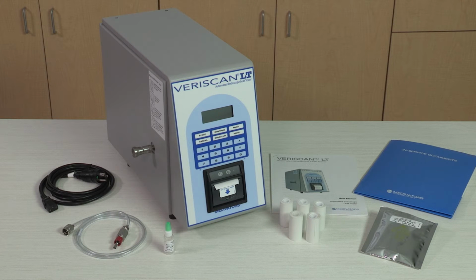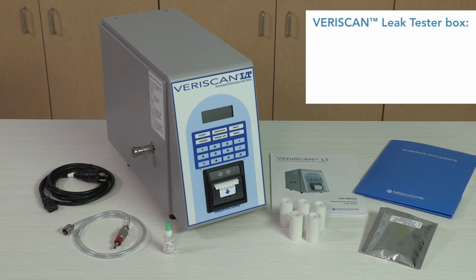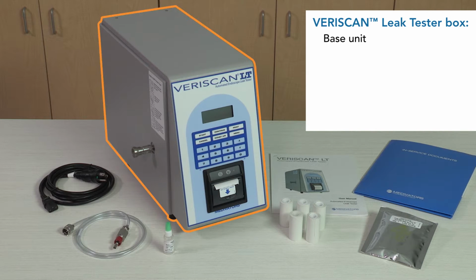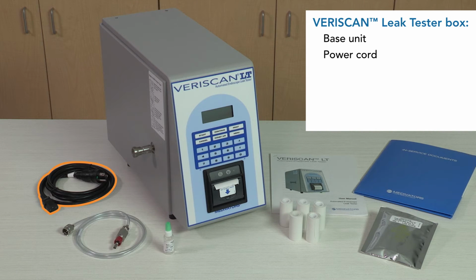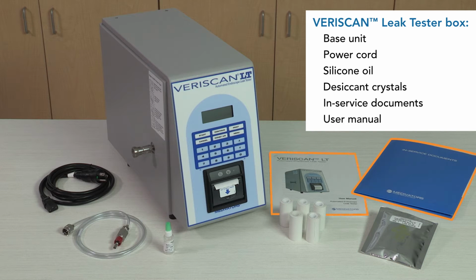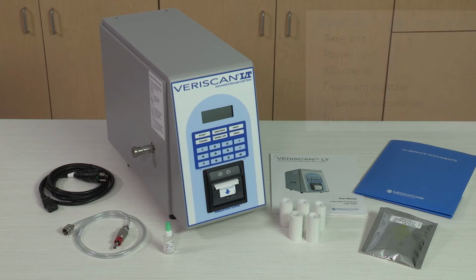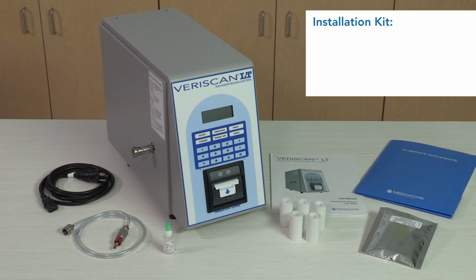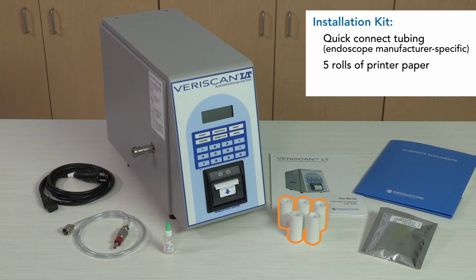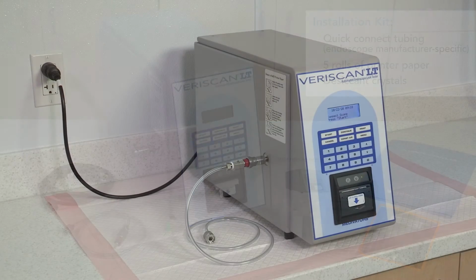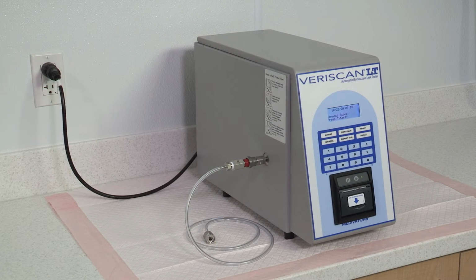Items for the VERISCAN Leak Tester are packaged in 2 boxes. The first box contains the base unit, power cord, silicone oil, desiccant crystals, in-service documents, and user manual. A second box, called the installation kit, contains the endoscope manufacturer-specific quick connect tubing, 5 rolls of printer paper, and a second bag of desiccant crystals. Let's take a closer look at the components and features.